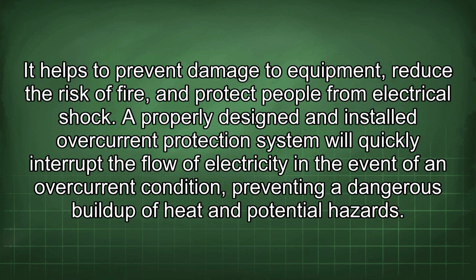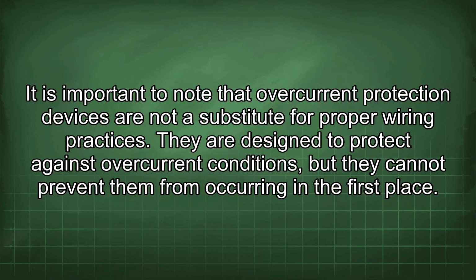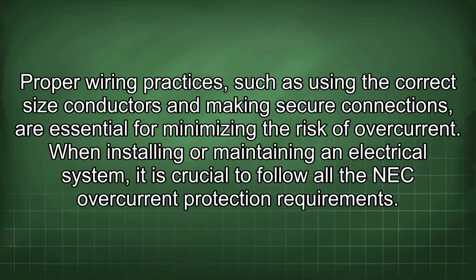A properly designed and installed overcurrent protection system will quickly interrupt the flow of electricity in the event of an overcurrent condition, preventing a dangerous buildup of heat and potential hazards. It is important to note that overcurrent protection devices are not a substitute for proper wiring practices. They are designed to protect against overcurrent conditions, but they cannot prevent them from occurring in the first place.